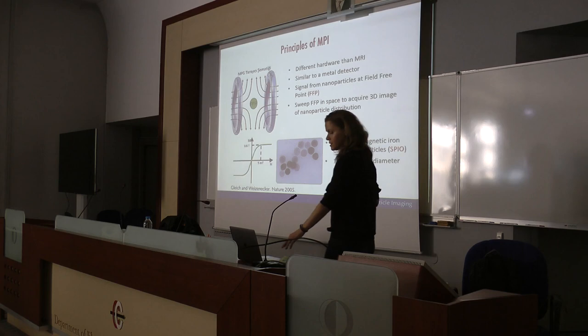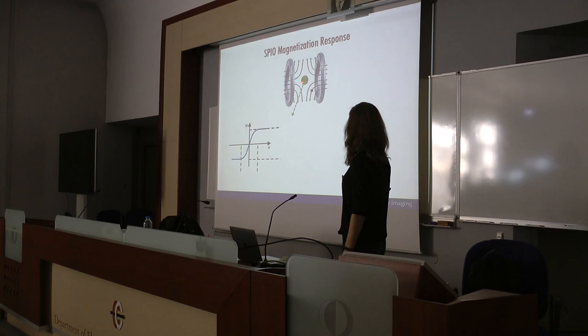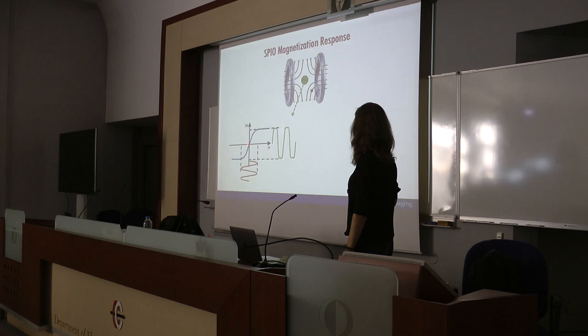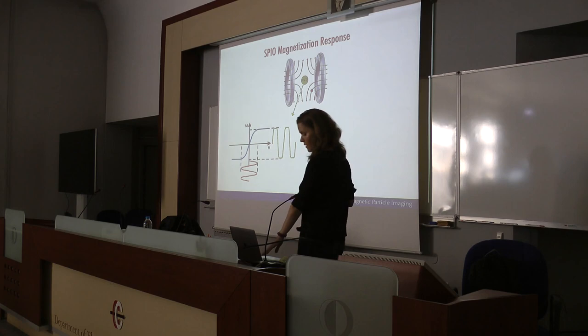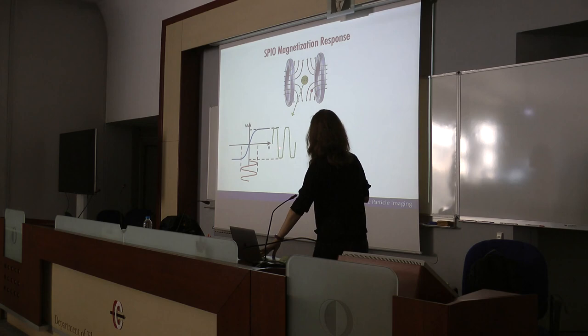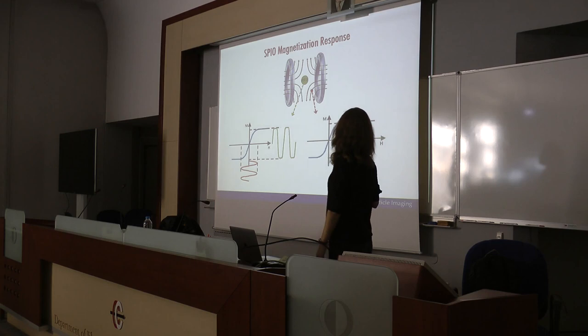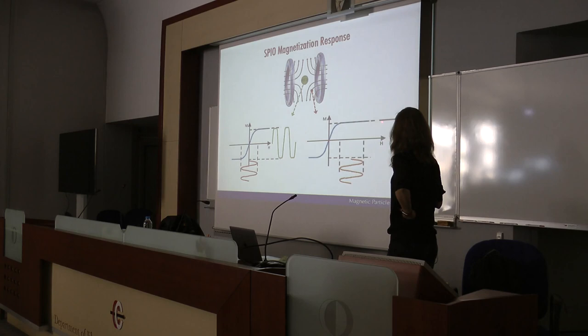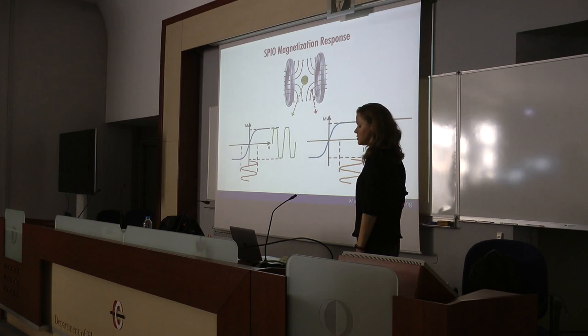If nanoparticles are placed at the field-free point, they start from zero magnetization. Applying a time-varying AC magnetic field causes the particles at the center to experience saturation in both positive and negative directions. The signal is inductively received as the time derivative of this magnetization. By contrast, nanoparticles placed closer to one of the magnets are already saturated — applying an AC field on top doesn't change their magnetization, so the time derivative is zero. We therefore get signal only from nanoparticles in the vicinity of the field-free point.